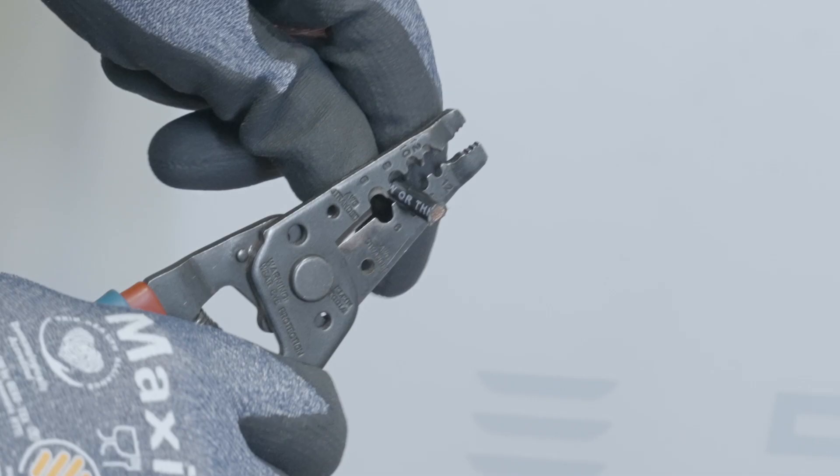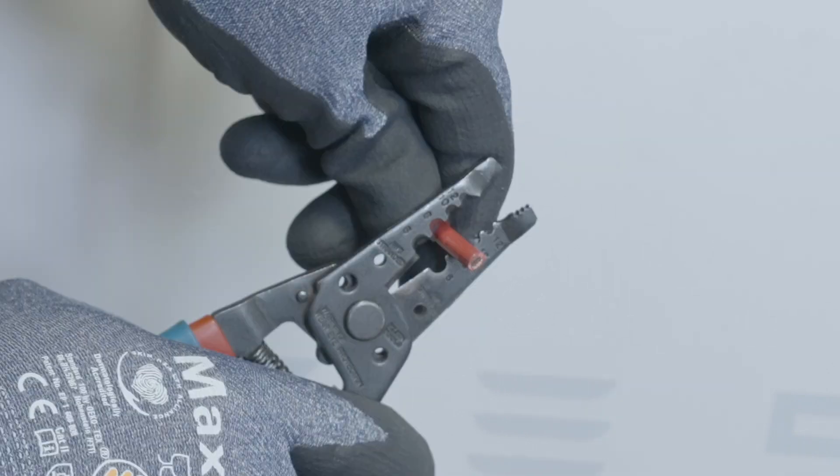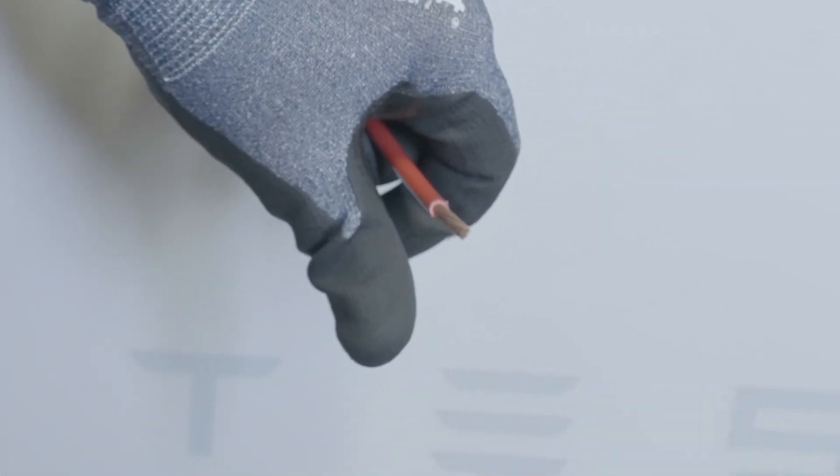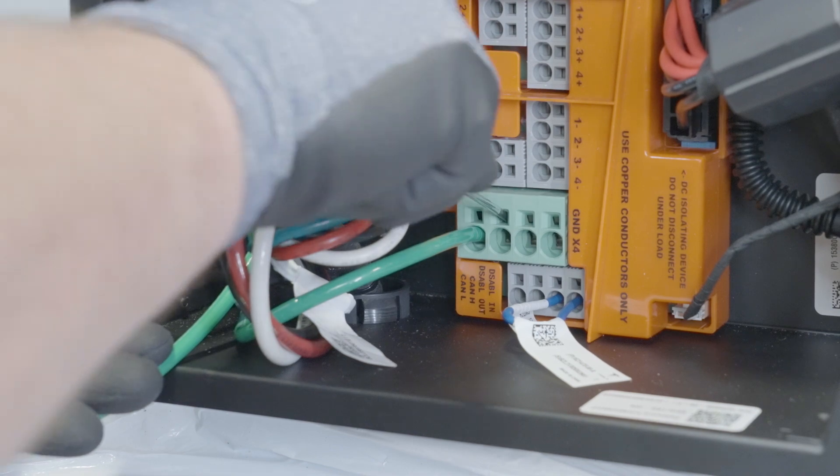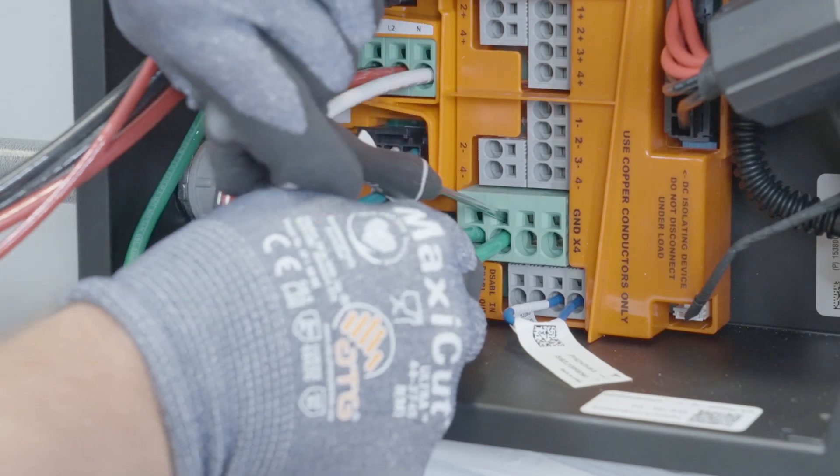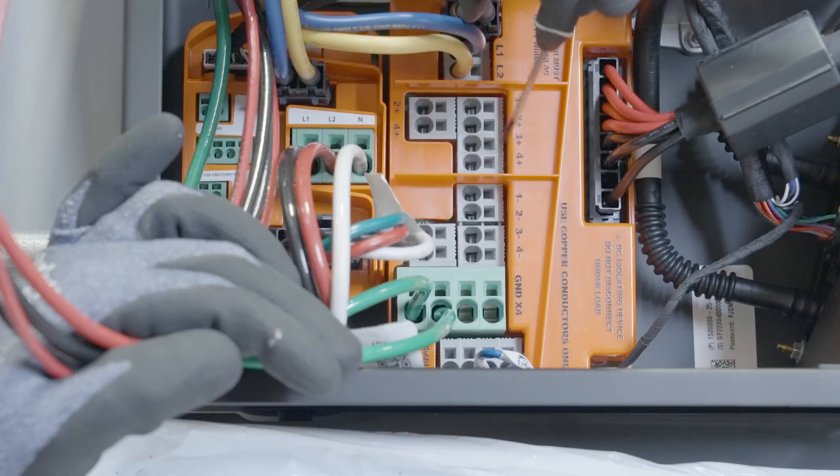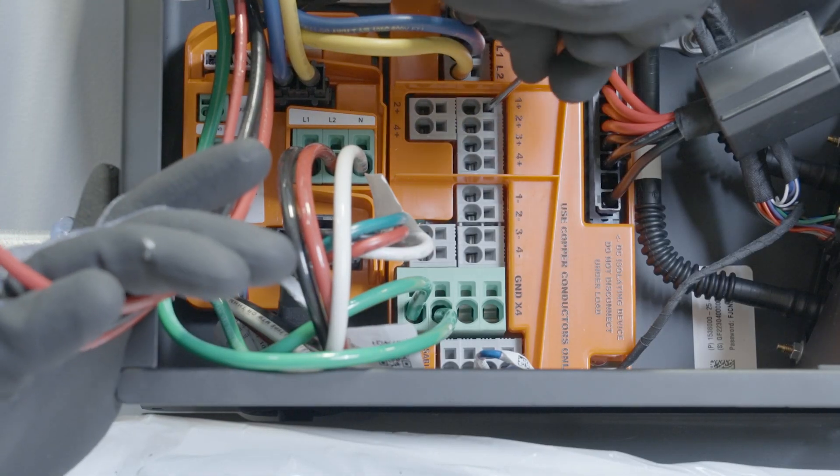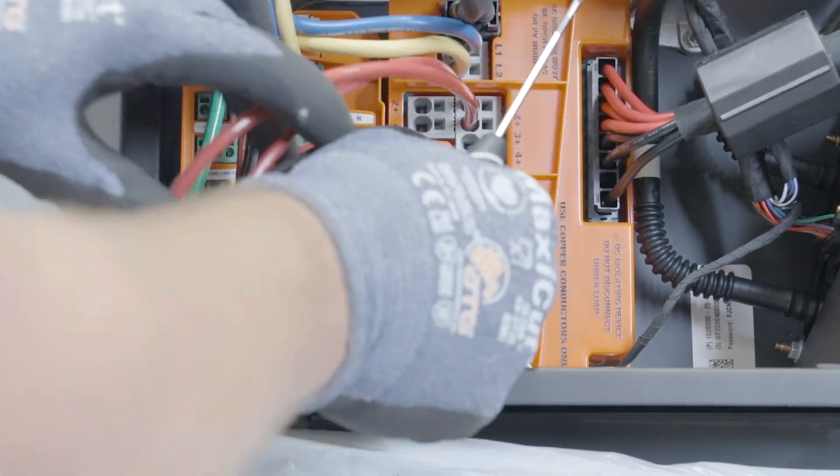Strip half an inch of insulation from each DC conductor. Similar to the AC conductors, insert a cabinet-tipped flathead screwdriver into the rectangular hole and terminate the equipment grounding conductors in the ground terminals. Terminate the positive and negative DC conductors in their respective terminals.